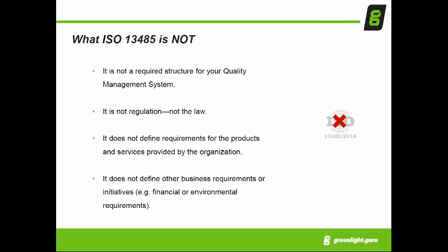That's not the law. ISO 13485, again, is a voluntary standard. It is not law. Now, it is based on regulations in Europe, Canada, United States. But adhering to ISO 13485 is not technically a regulatory requirement.